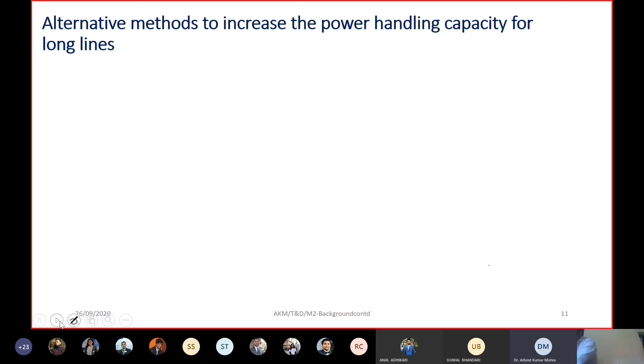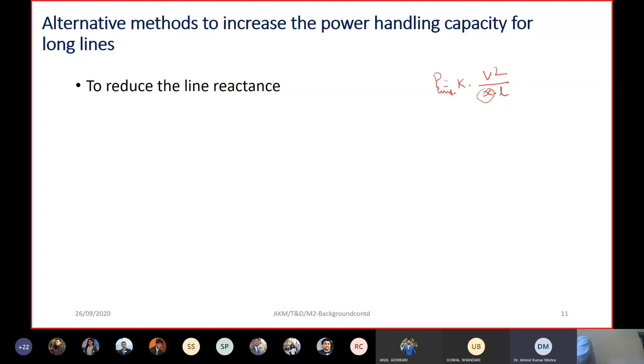One of the methods is called reducing the line reactance. You may ask me the question, just immediately, that reactance cannot be reduced. And the P limit expression, if you recall, is equal to some constant upon V square upon small x into L. I have told you that this x has no choice; we cannot vary it because this x is correlated with the line spacing and conductor size through the logarithm. And just to make this x half, you may have to reduce the spacing 100 times, which is not possible, right?